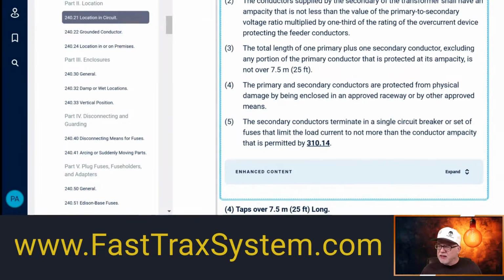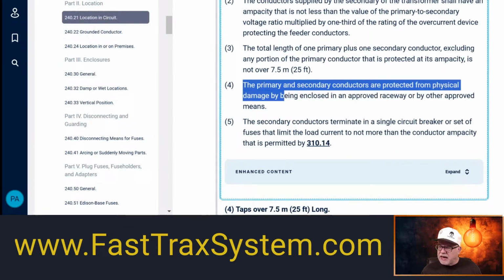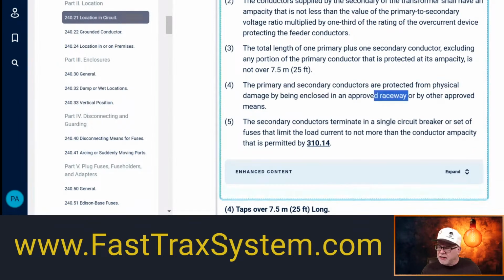All right, next it says, the primary and secondary conductors are protected from physical damage by being enclosed in an approved raceway. Okay, so now approved raceway is whatever your AHJ is happy with. It's any of the raceways approved, it's probably easier to say listed raceways, but some wireways are not listed, but they still would be considered something that would be okay to some AHJs, that type of thing. But approved raceway, and then it says, or by other approved means. Now, other approved means basically is whatever your AHJ is happy with.